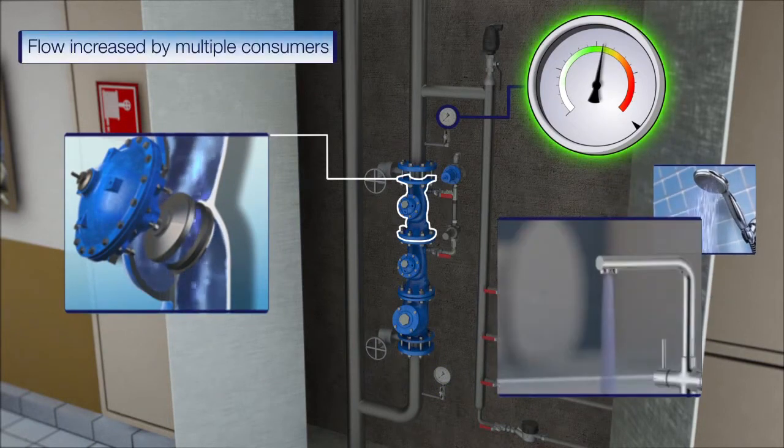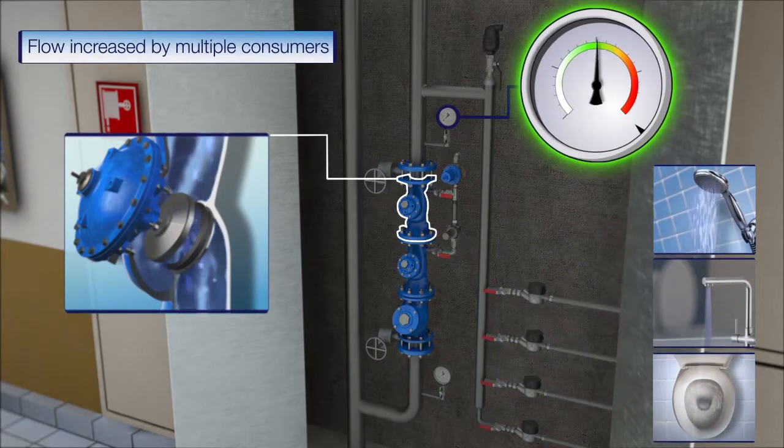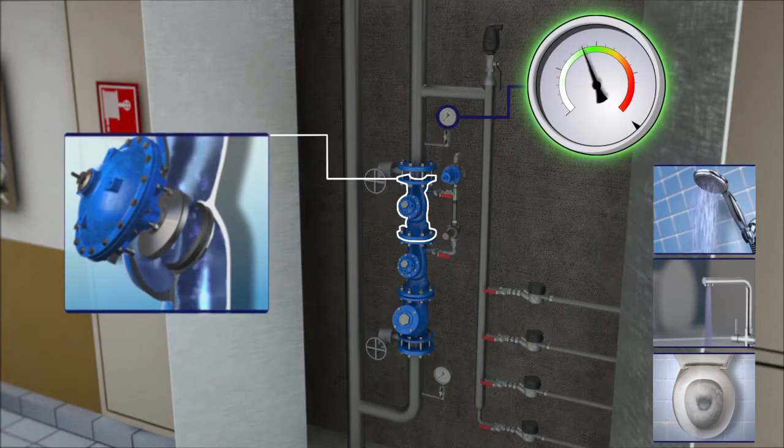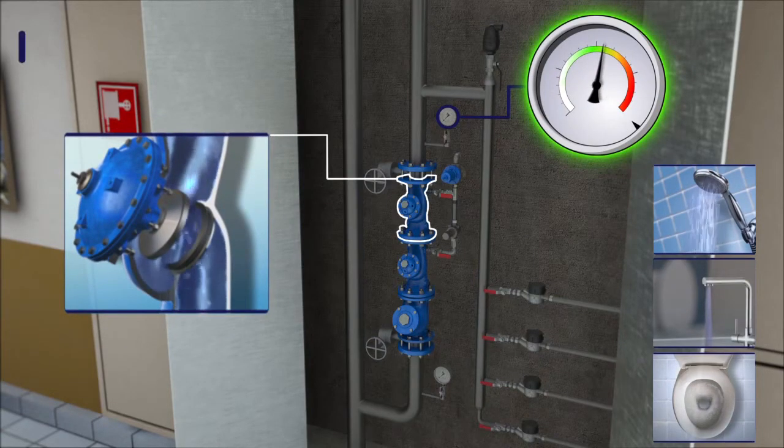In cases of high water demand, the flow rate increases dramatically and the downstream pressure plunges accordingly. The main valve increases its opening level so the downstream pressure returns to regular setting.